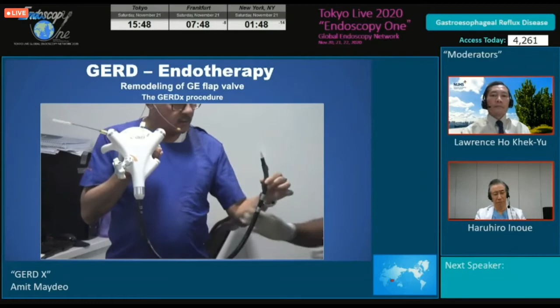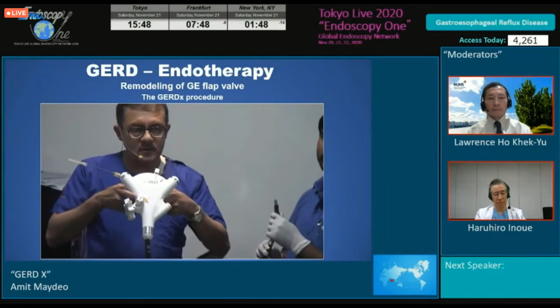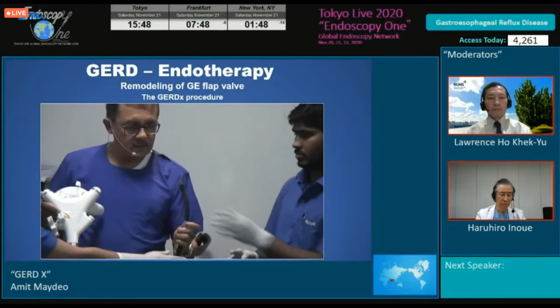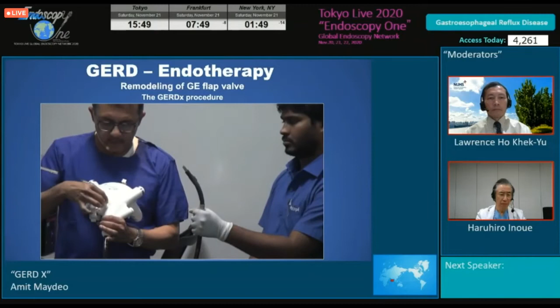So here you can see that I'm holding the GERDx device in the right hand and the shaft of the GERDx device in the left hand. And normally, while performing the procedure, it has been traditionally described that we have to hold the GERDx device by holding its two arms like this. However, in reality, when we perform the procedure, we have to actually rotate this device in a clockwise or anti-clockwise fashion so as to bring the arms properly for applying the full thickness plication on the lesser or the greater curvature of the stomach.